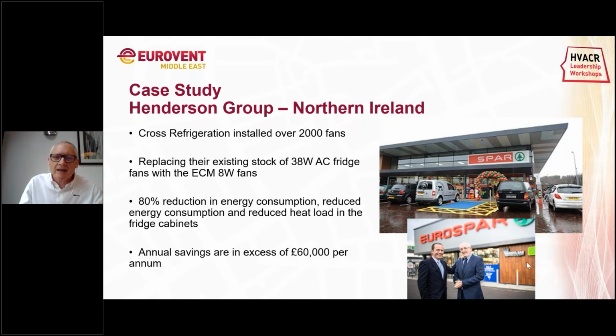They decided in association with fitting the EC fans, they would also replace the lighting to LED. And overall, they made some really tremendous savings. They had shaded pole AC motors, which are pretty inefficient, small 200 mil fans, and they replaced them with our ECM 8-watt fans. So they went from 38 watts per fan to 8 watts.